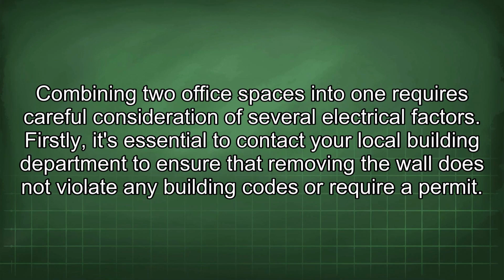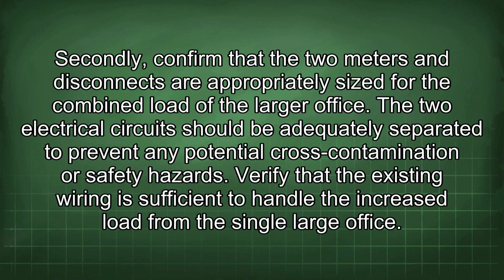Combining two office spaces into one requires careful consideration of several electrical factors. Firstly, it's essential to contact your local building department to ensure that removing the wall does not violate any building codes or require a permit. Secondly, confirm that the 2 meters and disconnects are appropriately sized for the combined load of the larger office.